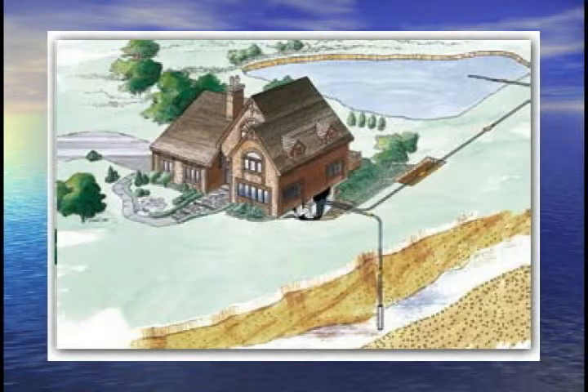If we have a summer that we might not have much rain and have a drought, and your water tables change, and the amount of water that we were pulling out of your open loop pump and dump system changes, it also changes the ability to cool and or heat your home. Worst case scenario is that the well actually goes dry, and now you have no means of heating and cooling the home. That's why the previous 3 types of installations were all closed loop, and those are going to be the preferred installation type because we can take Mother Nature out of the equation.